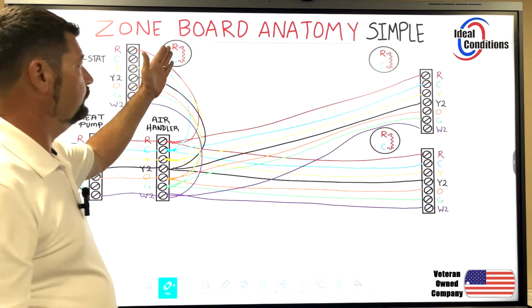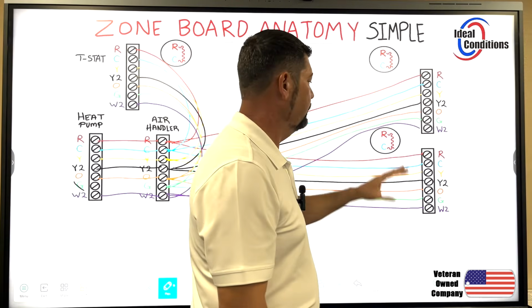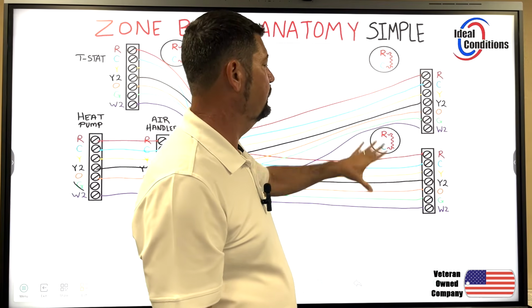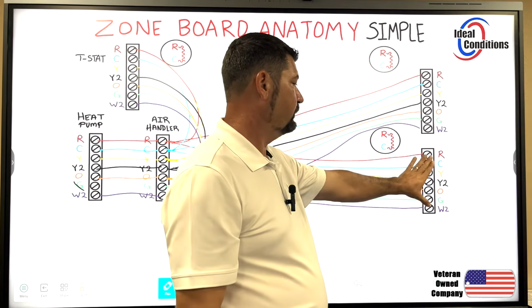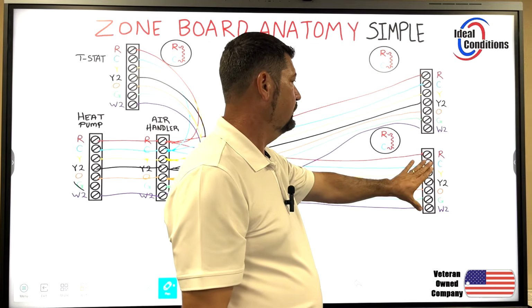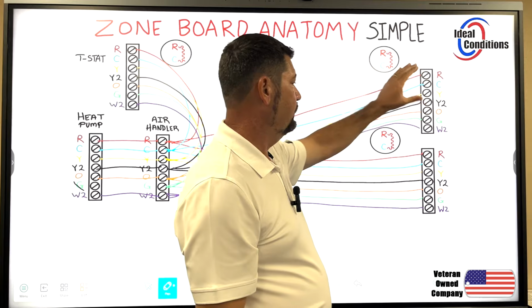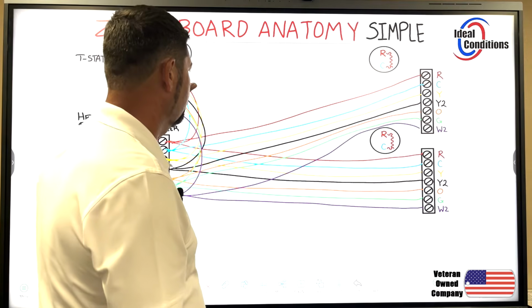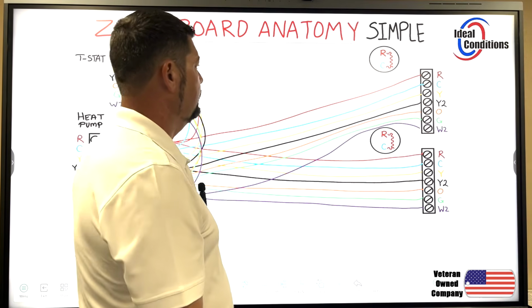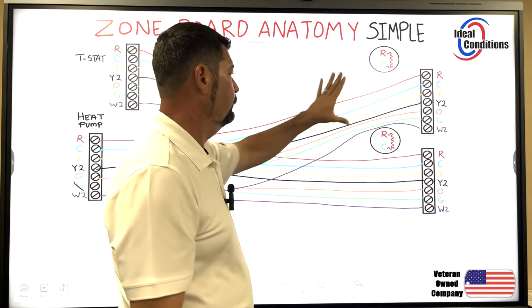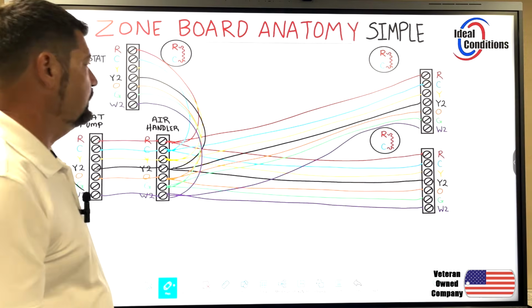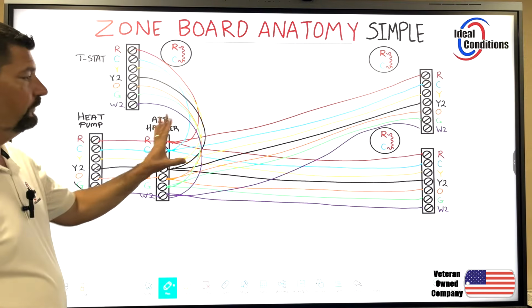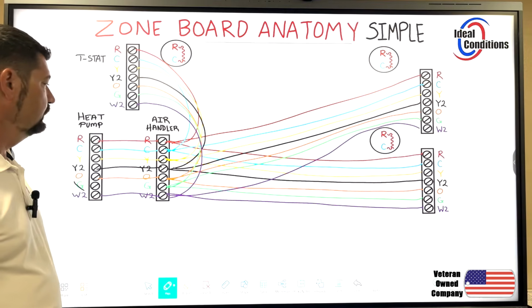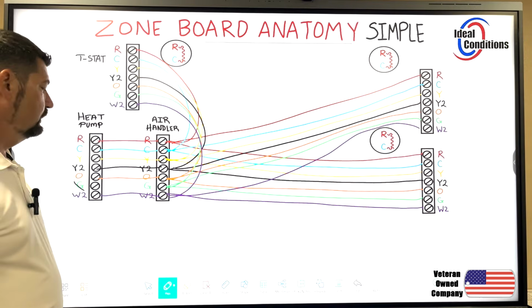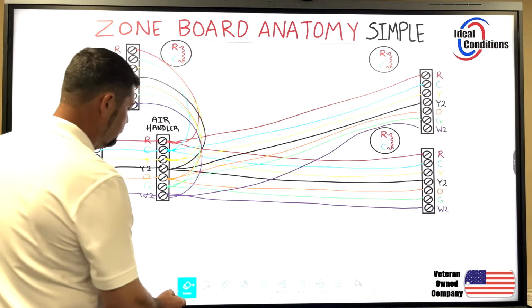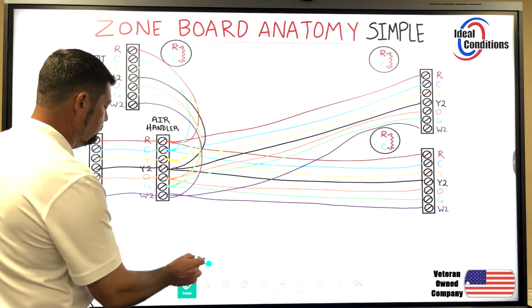These dampers can't close because there's nothing here to tell those dampers if I only want this thermostat to call and not this one or that one. There's absolutely no way to have those areas or zones shut down. So this is just ridiculous, and you would never do this. We're going to go ahead and erase this because it's not practical.